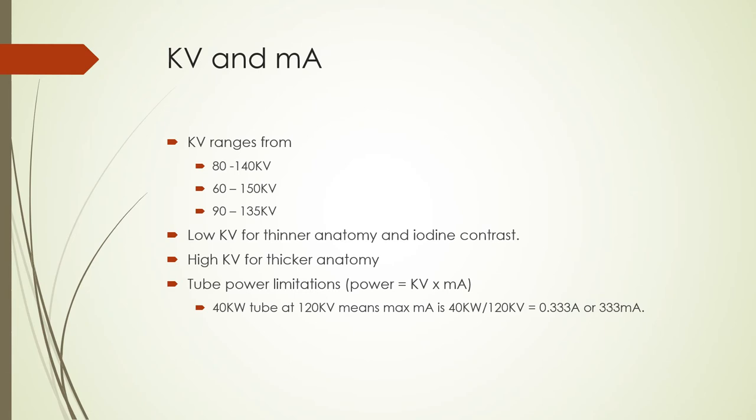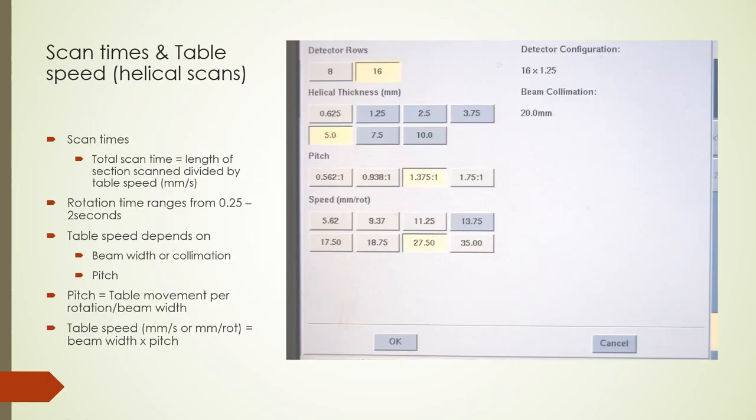For example, with a 40 kW tube at 120 kV, the maximum mA is 40 kW divided by 120 kV, giving 333 mA. The minimum rotation angle needed to form a CT image is 180 degrees plus the fan angle — about 240 degrees for a 60-degree fan angle. For helical scans, scan times depend on rotation time, beam width, extent of the scan, and pitch factor. Pitch is table movement per rotation divided by beam width.